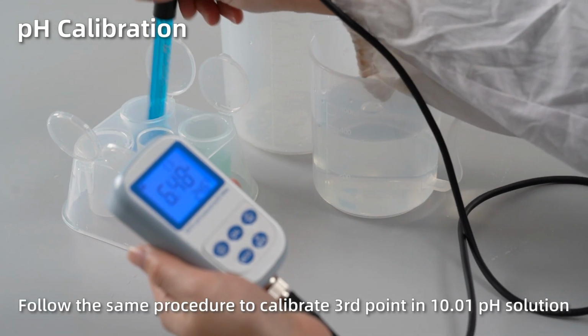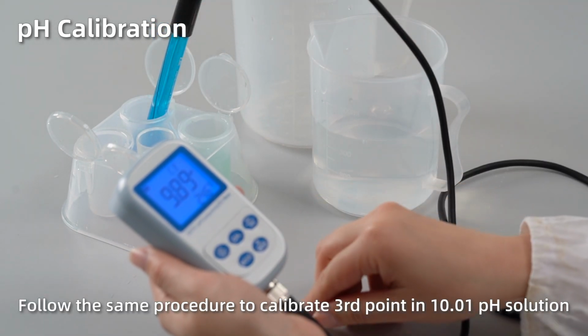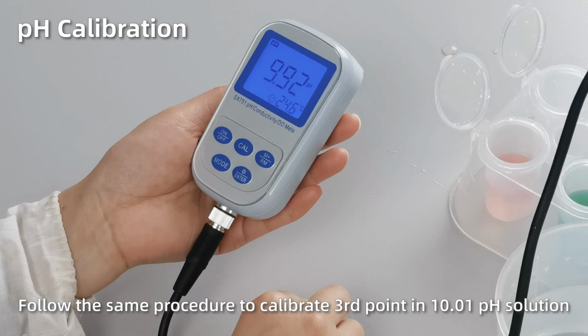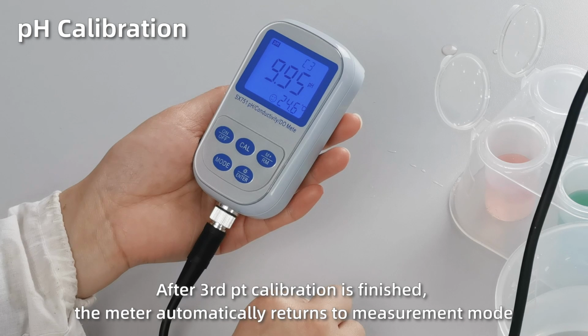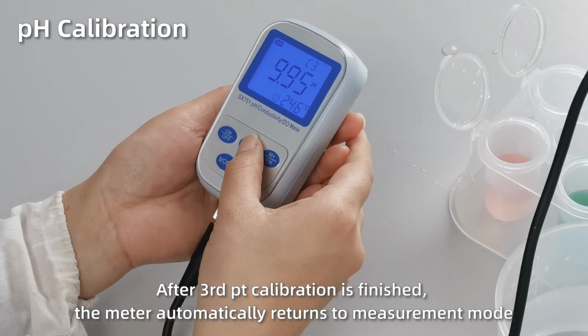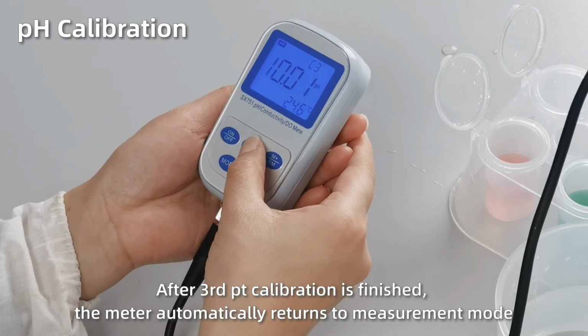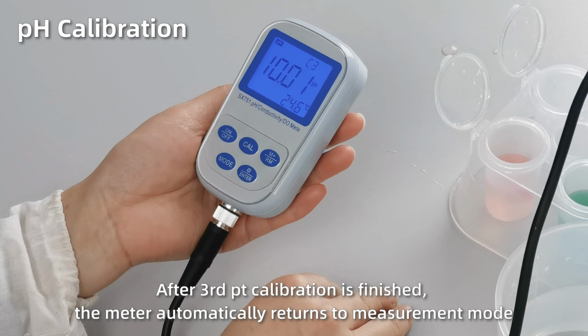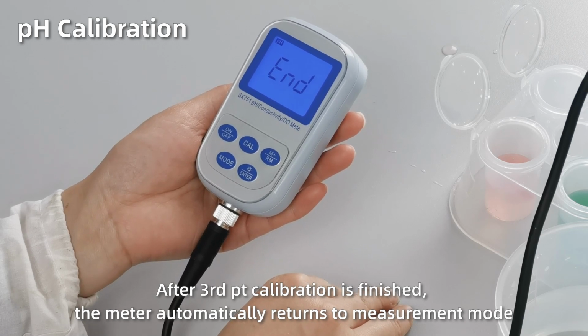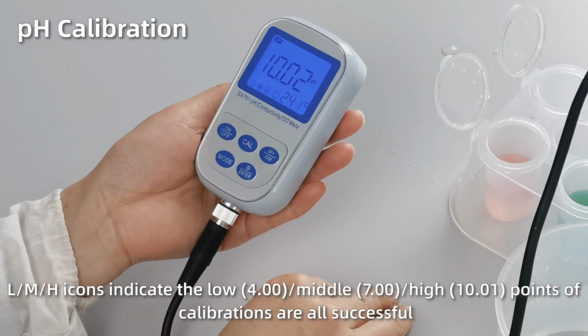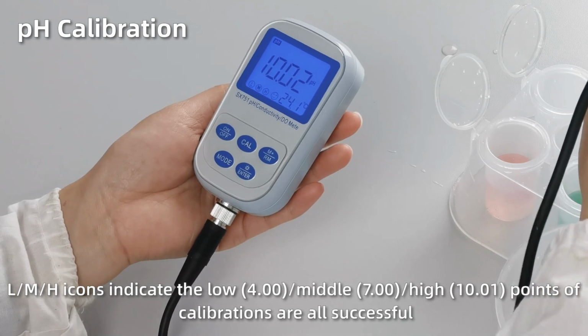Follow the same procedure to calibrate the third point in pH10 solution. After it's finished, the meter automatically returns to measurement mode. The L, M, H icons at the bottom left indicate the 3 points of calibrations are all successful.